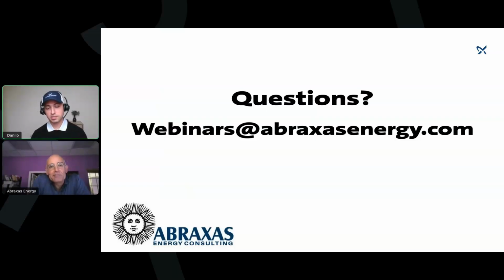That's a very good question, and it's actually really hard to measure that, right? To get data on that. As being a Grundfos person, I'm only talking about pumps. But again, as I was in the Hydraulic Institute course yesterday, we started looking outside of pumps. And one way of increasing energy savings, right, reducing energy consumption, is also increasing the size of pipes, right? You could increase the size of your pipes, and now you're reducing the pressure loss. So now the demand on your pump is lower, or you can also downsize your pump.